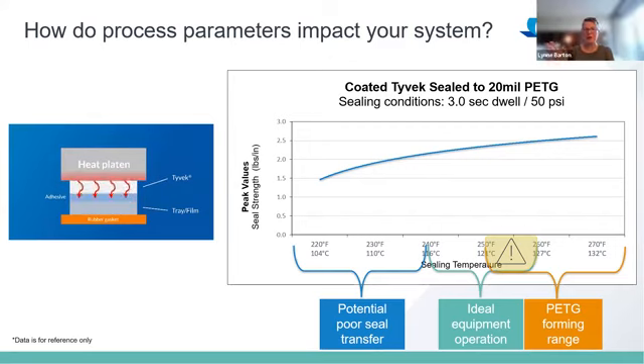I like to say, and anybody who's sat with me for more than 5 seconds has heard me say, low and slow is really the best practice. You want to make sure you understand what the individual material process windows are, and what the process window overlap is—understanding where the adhesive is going to activate, what the PETG process window is, and then targeting that on the sealer. One thing I always try to make people understand is cycle rates. There can be heat buildup in that gasket if you start cycling the sealer really fast and building up heat. That's where the temperature can start to creep up, activating that PETG tray and causing curling, because the temperature in the system really likes to be nice and stable. So low and slow is the mantra we use in the medical device industry for the most repeatability.